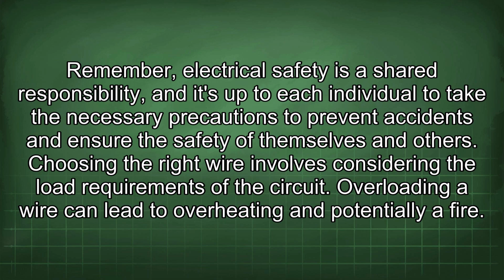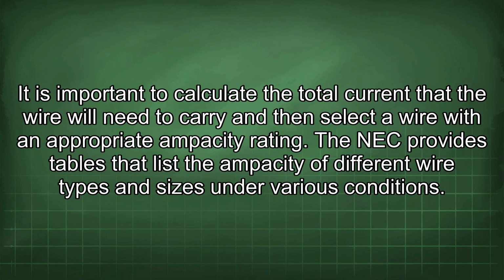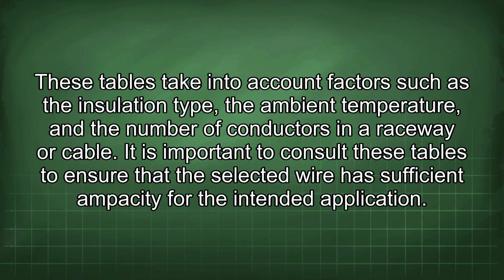Choosing the right wire involves considering the load requirements of the circuit. Overloading a wire can lead to overheating and potentially a fire. It is important to calculate the total current that the wire will need to carry and then select a wire with an appropriate ampacity rating. The NEC provides tables that list the ampacity of different wire types and sizes under various conditions. These tables take into account factors such as the insulation type, the ambient temperature, and the number of conductors in a raceway or cable. It is important to consult these tables to ensure that the selected wire has sufficient ampacity for the intended application.